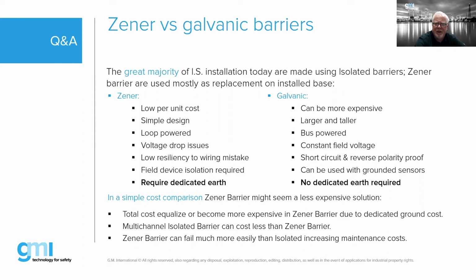Sometimes with the maintenance of Zener barriers, we find that we'll blow out the fuses or do something to it. It's very easy to do that. So with Zener barriers, we have to treat them with kid gloves during that initial startup. That's not to say that we can't damage a galvanically isolated barrier, but with Zener barriers during that initial startup, we have to be very, very careful because we will blow a fuse. Generally speaking, once a fuse is blown in a barrier, we typically have to replace the barrier.